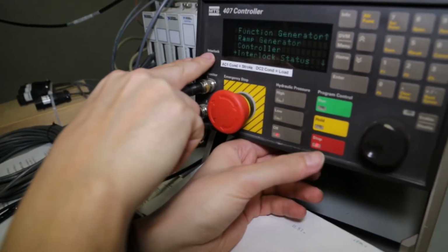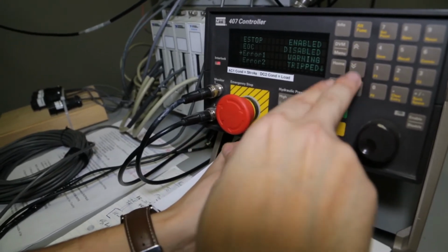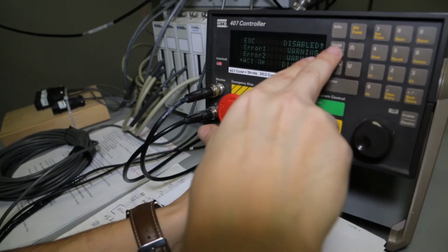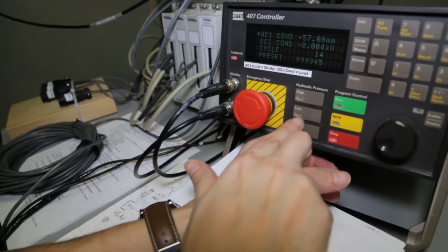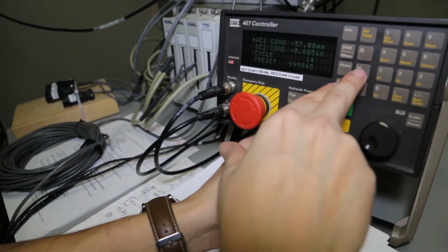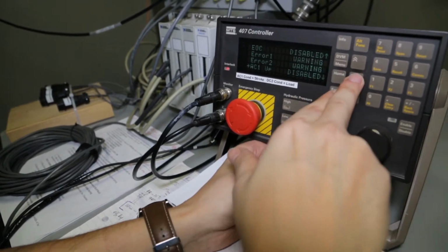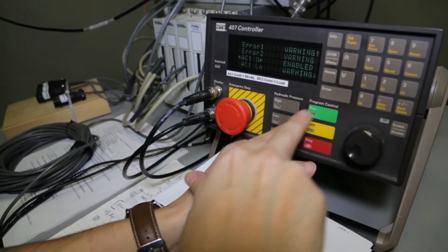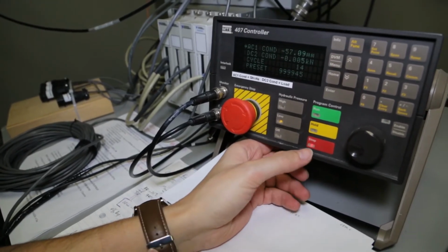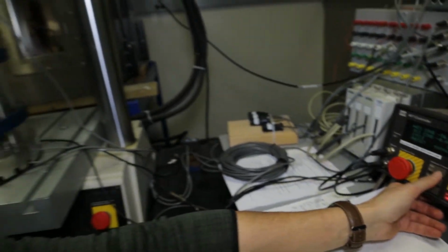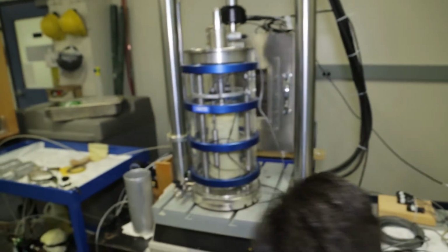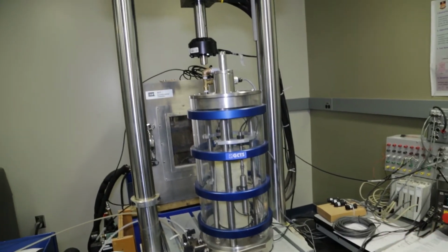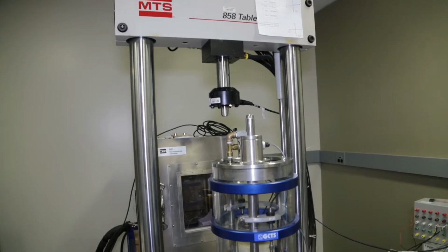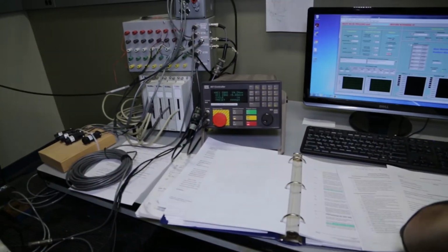I go down to interlock status because there's a safety measure that is triggered right now. I need to take it off so that I can bring the piston up. Now it's on off. I just put it on low first. High hydraulic pressure lifts it up faster, but make sure I don't keep it on high all the way because it can get jammed on the top.